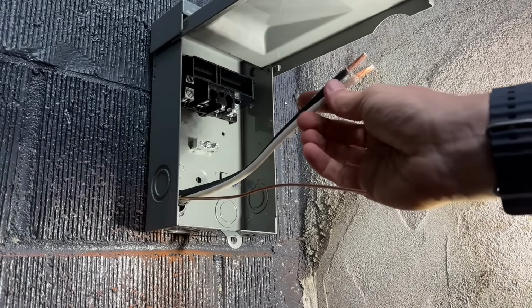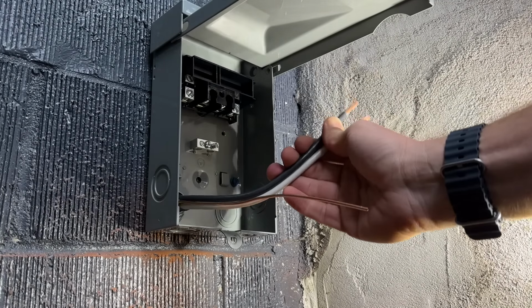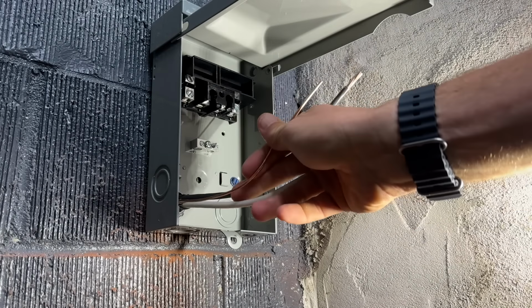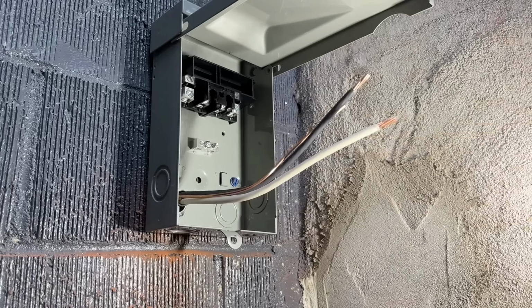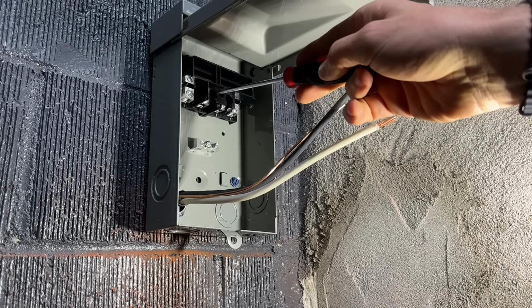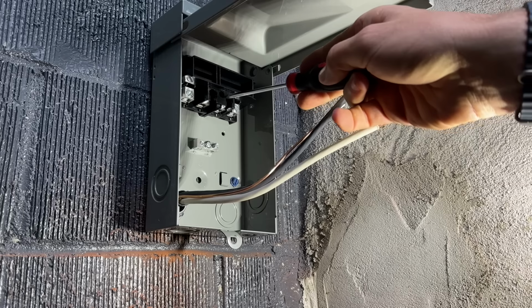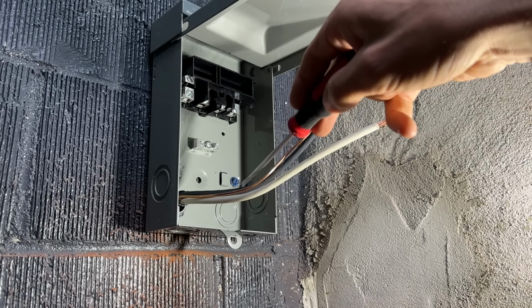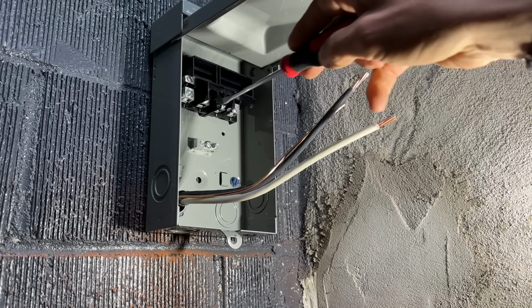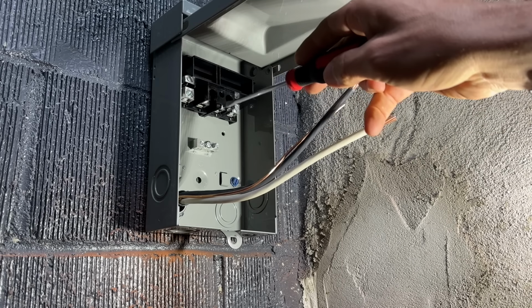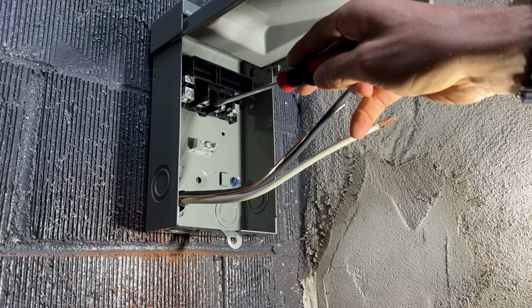So then out at the disconnect, we have our 2 6 gauge conductors ready to go for each phase, and then a 10 gauge ground, bare ground coming out. Now in the middle section here are going to be the 2 line sides. So that is going to be this black conductor to the outside, white conductor to the inside. You could flip flop those around, it doesn't matter. And we'll tighten those up.